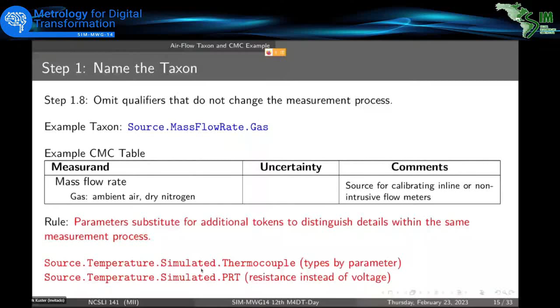It's similar to calibrating thermocouples. There are various types of thermocouples, but the type can just become a parameter under one taxon, because it's always a voltage versus a temperature if you're simulating a thermocouple. Whereas if you're simulating a platinum resistance thermometer, it's a resistance versus a temperature, so that would be a separate taxon. So we drop the ambient air from the taxon, and we have our taxon completed.